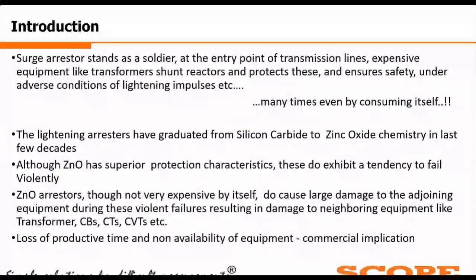The ZnO arrestor, though not very expensive by itself, can cause large damage to the adjoining equipment if it fails, because a ZnO block failing, or the surge arrestor failing, is nothing but the blasting of the surge arrestor. What happens if the equipment is blasting is that parts of it damage the neighboring equipment like transformer, breaker, CT, PT or CVT, and all other things. And we can have a very large loss of productive time and non-availability of other equipment. So ultimately we will be facing commercial implications.